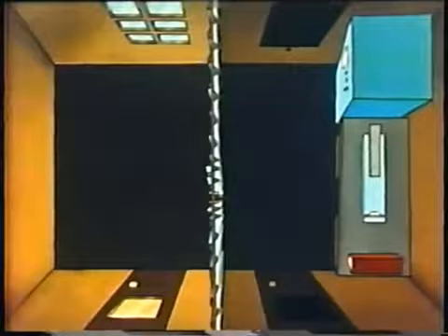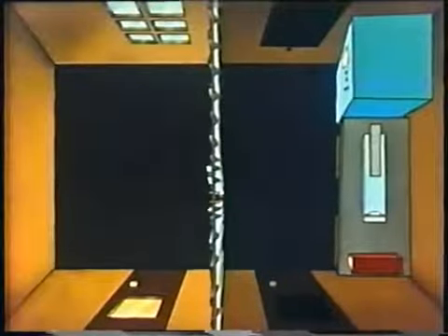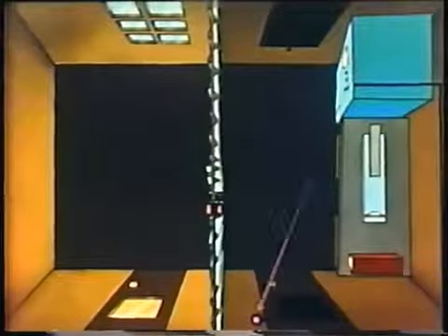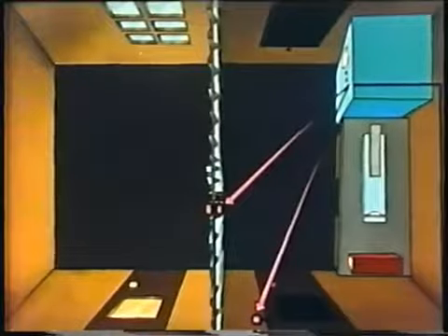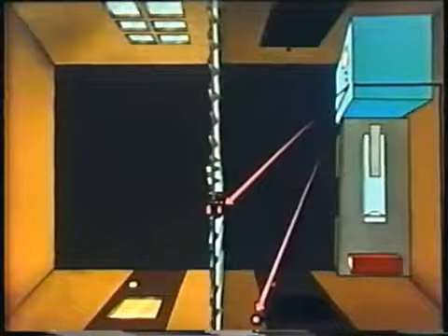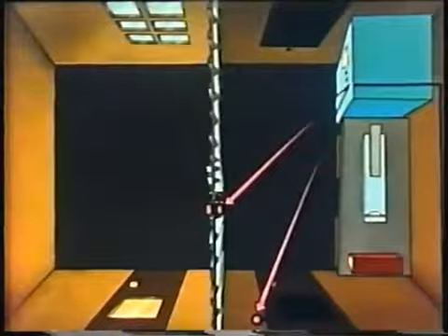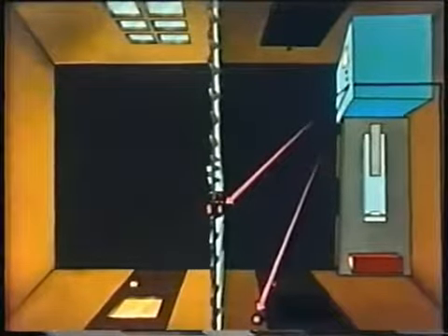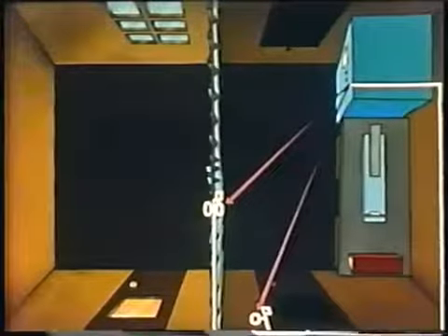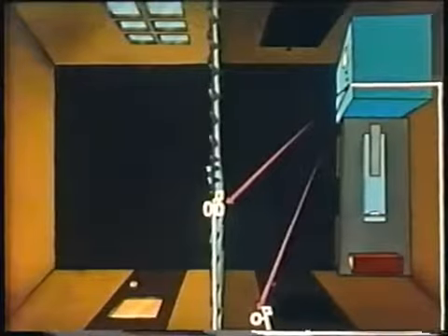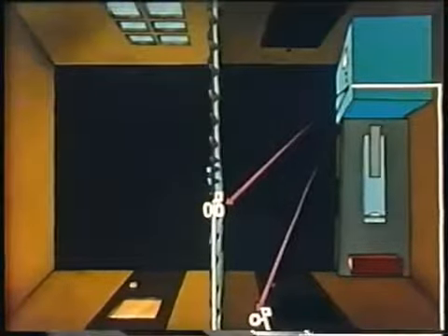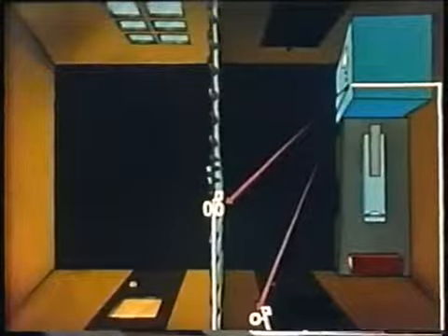All windows and door windows should have blackout curtains or some other absorbent material. Safety interlocks should be provided for all doors, the primary entrance and the secondary entrance, such as the isolating screen. The interlocks are connected to the power supply. When the power supply is turned on, the interlock switches lock the doors so that no one can enter during laser operation except in emergencies. The lock should not prevent quick exit from the room.